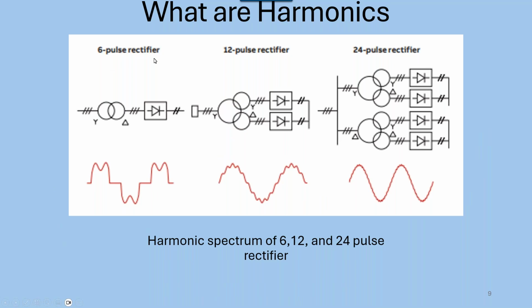So a lot of you may have heard of a 6-pulse rectifier. I think of this as like rabbit ears. So if you're looking at a waveform and you see these rabbit ears, that's a 6-pulse rectifier. Here's what a 12-pulse rectifier looks like, and this is what a 24-pulse rectifier looks like. See how smooth this 24-pulse is?